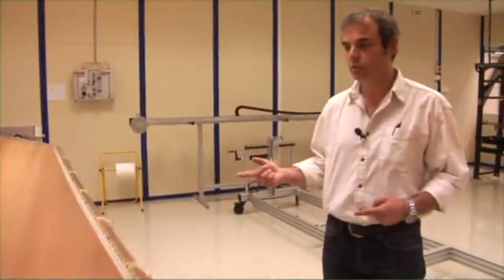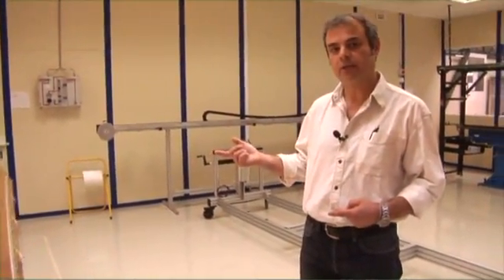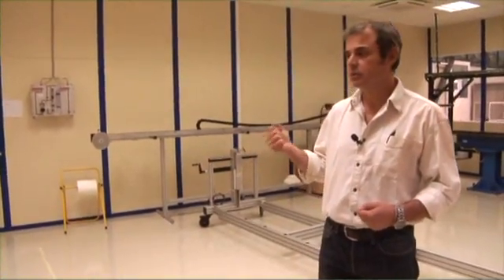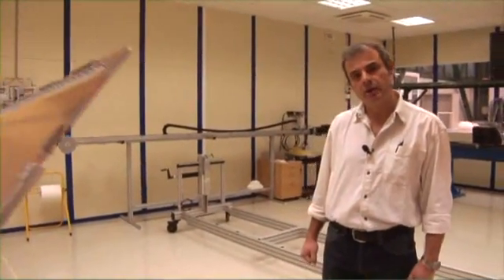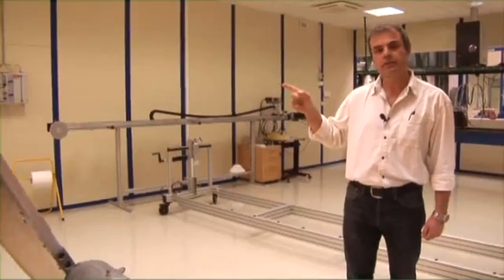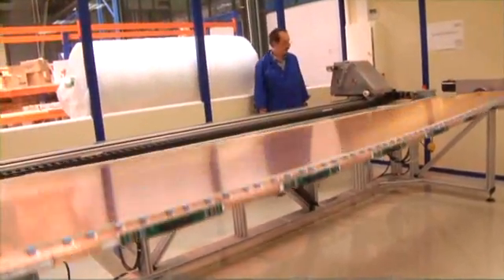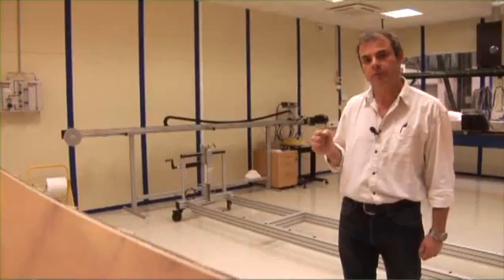So the next step is to wind wire around the anode panel. It takes about 2.6 km of 50 micron gold plated tungsten wire and it is about 1,000 wire winds that go around the panel. It takes about 4 hours to complete one panel.